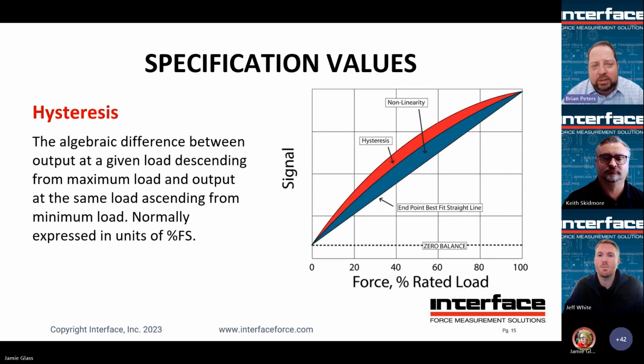All right, hysteresis. Hysteresis is the difference in output on a descending load versus what the sensor produced on the ascending. What that means is you increase load up to full scale, and then you revisit one of the same points you took on the ascending side as you're releasing the load, and that output might not be exactly the same as it was on the ascending side. That's going to be defined as a hysteresis value, and that's going to be percent of full scale as well. So you can understand too, maybe that doesn't apply for my application if I'm only doing a single load and I want to track the force that's being applied through that test, right? So there's hysteresis. Next one.